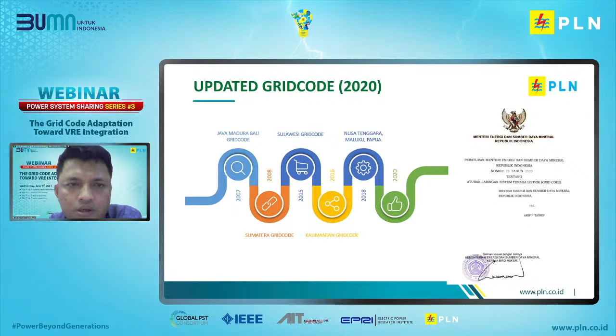This is critical support for VRE integration. The difference between the old and new grid code is the addition of variable operating time to the frequency range. It used to be only a frequency range in the 2008 grid code for Sumatra. I believe Sumatra, Java, and other systems basically adopt the same grid code, the Java Bali grid code, which we implement in each system.